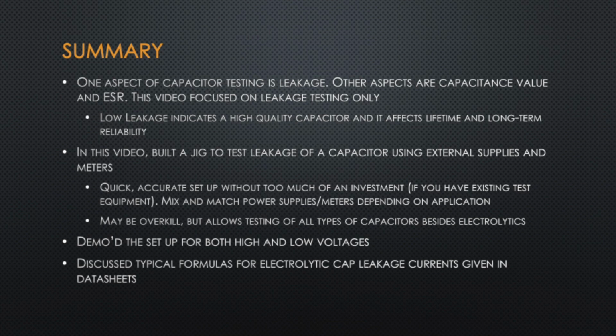I think there's a lot more to be learned about testing of leakage, how you measure it, how long you measure it for, what kind of voltages you apply, and the safety factors that need to be considered. And finally, we discussed the typical formulas that are used for electrolytic cap leakage currents given in data sheets. Different manufacturers have different formulas, which probably play to their strengths. But for us, these are just starting points, and with this kind of a setup, you can confirm that these capacitors are meeting their specifications, and they are also safe to use in a given application.